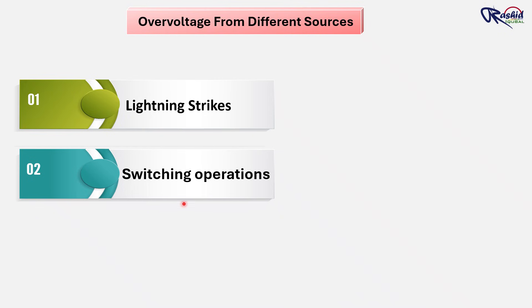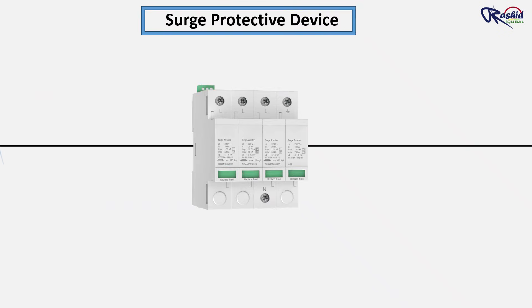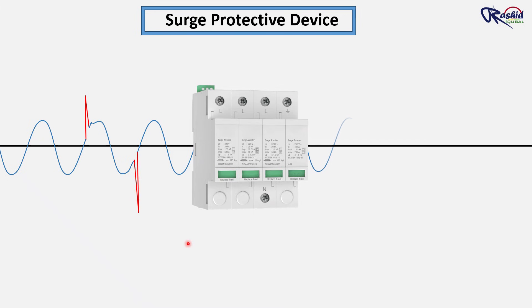Switching operations include turning on or off heavy motors, elevators, or HVAC systems. There is also fault clearing — when a breaker or fuse disconnects a fault like a short circuit, the sudden interruption can create a small voltage spike. This spike lasts a very short interval but can still travel through the system. The SPD quickly diverts this spike to earth, keeping the equipment safe.